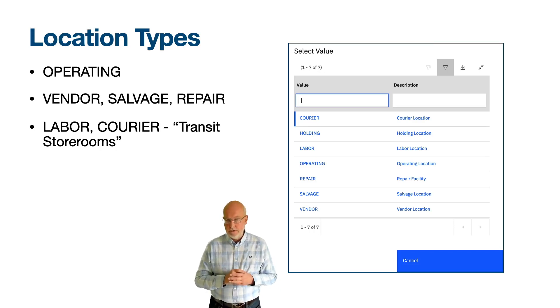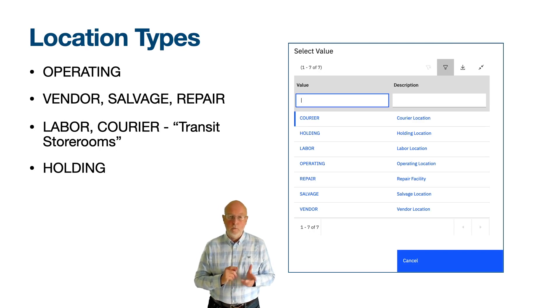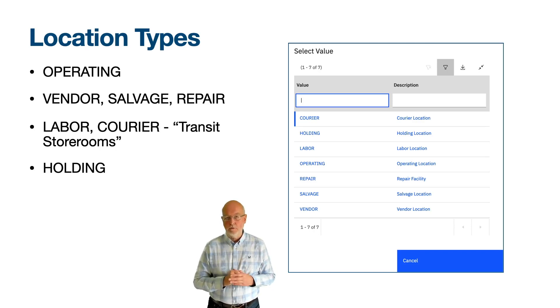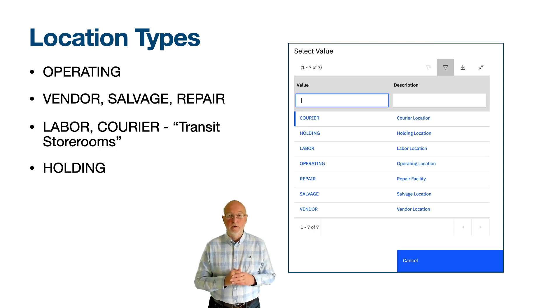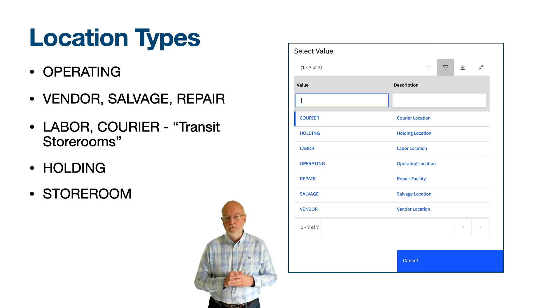Every Maximo site must have one and only one location of type Holding. This is used for the receipt of goods that are waiting to be inspected or serialized. Often we call the holding location Receiving, and it is in the Receiving application — part of the purchasing module — where you will come across this. There is one other location type called Storeroom, which is used in inventory, but you need to be in the Storerooms application to create these records.